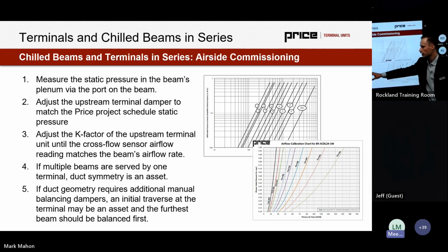Now, a couple other points here, and I'll talk on these in a couple more slides, so I'll be brief with them. But if multiple beams are served by one terminal, ideally some level of duct symmetry is an asset. So rather than having a terminal with a super close beam, a medium beam, and a super far beam, if it's possible to do our duct work to have it split like a trident almost, we're going to find that those three beams are easier to balance with one another just because the duct pressure drop is similar. So we don't need as much influence from a balancing damper, which is a really nice benefit.